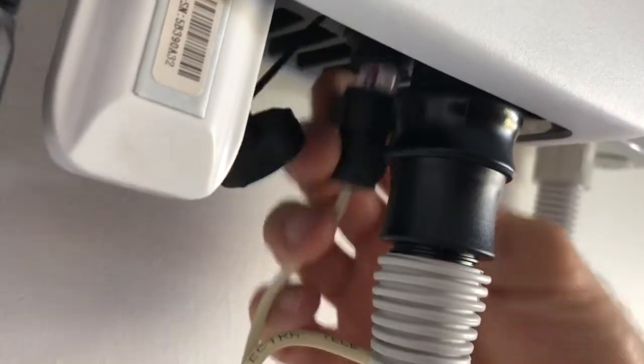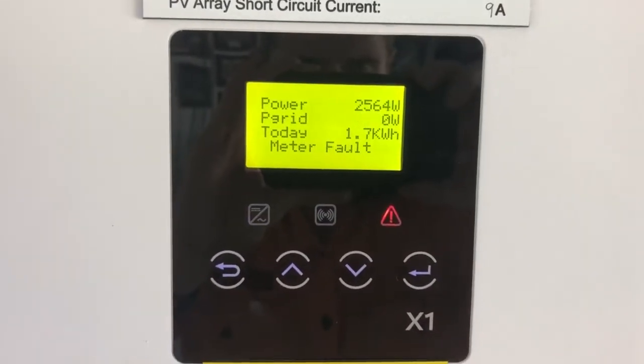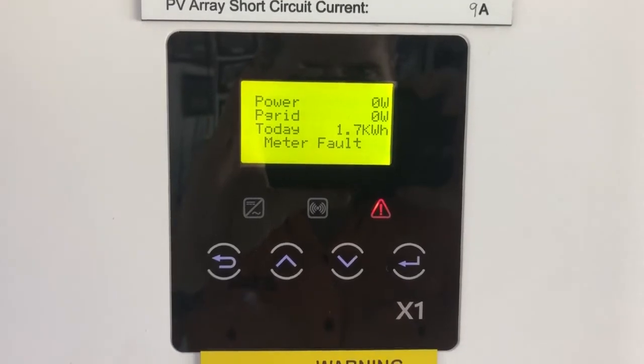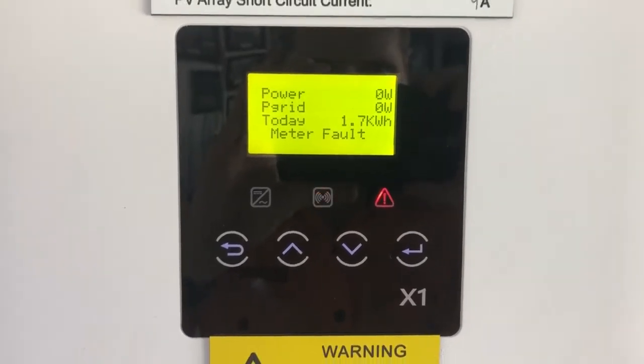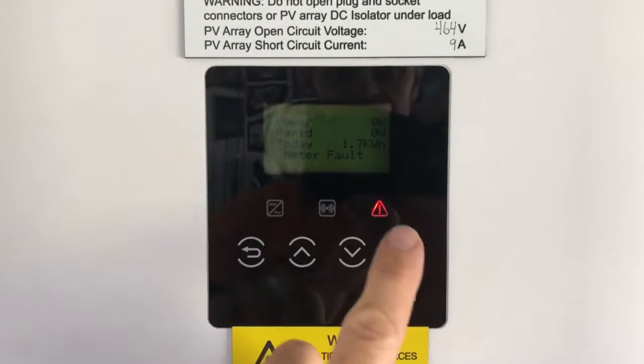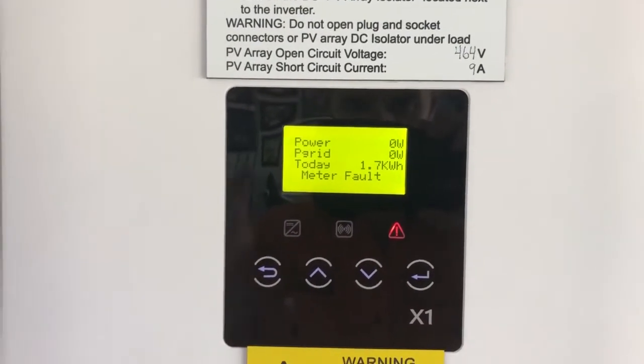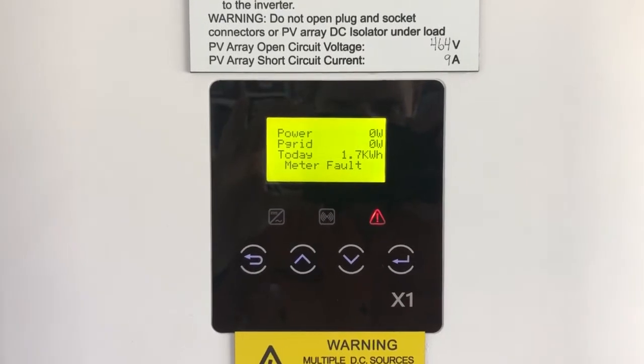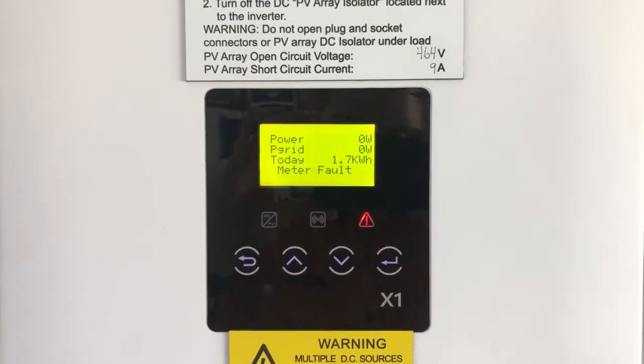I'm just going to unplug that and watch what happens on the screen. We see it's come up with a meter fault and we've got the red fault light on, so the system's not producing any power. What's going to happen is it will go from the meter fault and then try to reboot the system, but it's not going to work because it keeps seeing this meter fault.